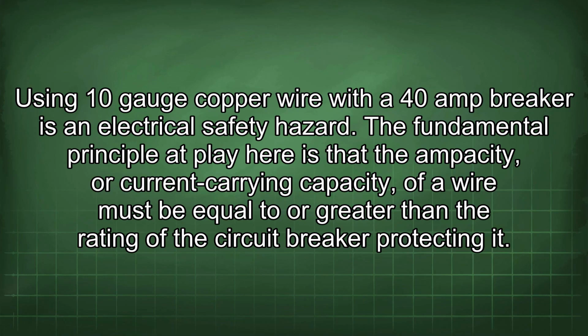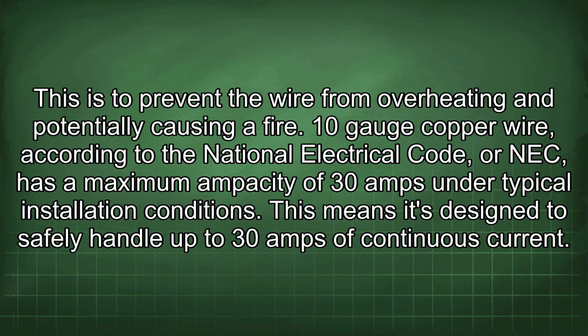Using 10-gauge copper wire with a 40-amp breaker is an electrical safety hazard. The fundamental principle at play here is that the ampacity, or current carrying capacity, of a wire must be equal to or greater than the rating of the circuit breaker protecting it. This is to prevent the wire from overheating and potentially causing a fire. 10-gauge copper wire, according to the National Electrical Code, or NEC, has a maximum ampacity of 30 amps under typical installation conditions. This means it's designed to safely handle up to 30 amps of continuous current.